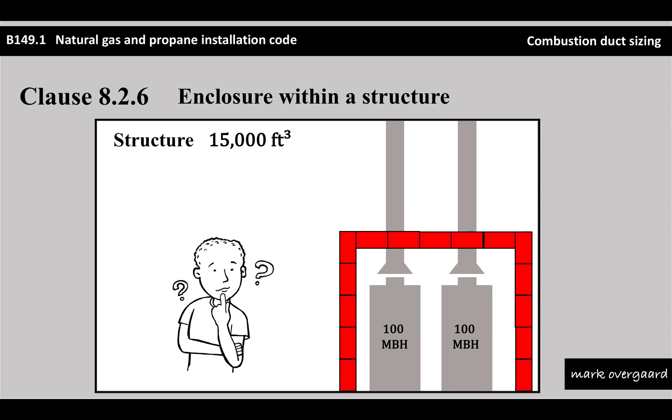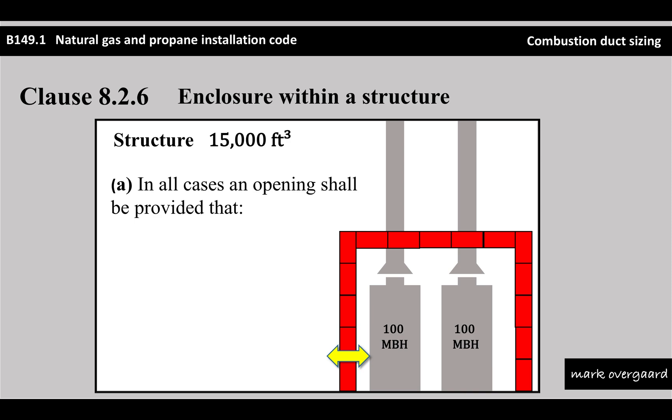Now we get back to Mike. He's thinking, well, we had air from the outside to the inside before - that's great. But because we've put this enclosure around the two appliances, where's the air coming from outside to inside into there? We've got ourselves an issue, and he's right. There is an issue, and that's where the clause comes into play. This is how you size that opening.